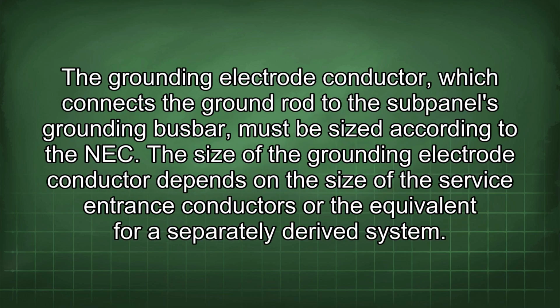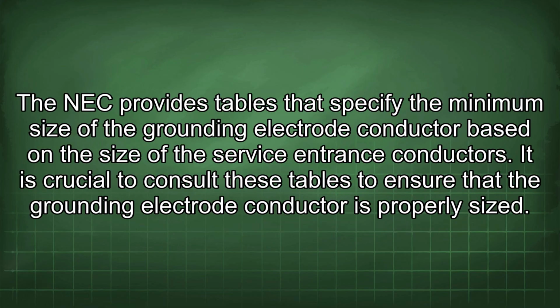The grounding electrode conductor, which connects the ground rod to the subpanel's grounding bus bar, must be sized according to the NEC. The size of the grounding electrode conductor depends on the size of the service entrance conductors or the equivalent for a separately derived system. The NEC provides tables that specify the minimum size of the grounding electrode conductor based on the size of the service entrance conductors. It is crucial to consult these tables to ensure that the grounding electrode conductor is properly sized.